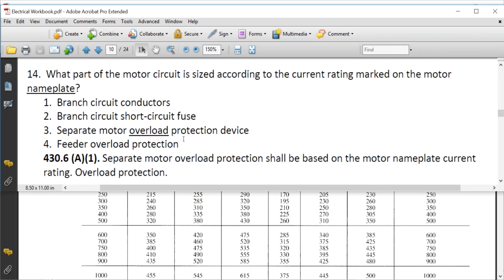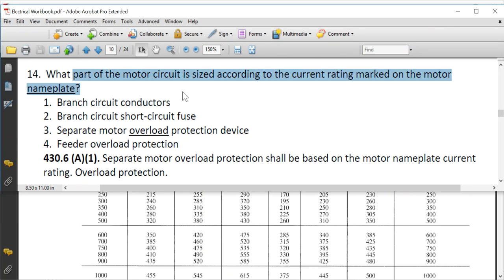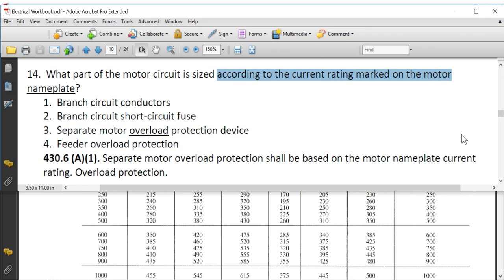What part of the motor circuit is sized according to the current rating marked on the motor nameplate? The correct answer is the overload. The overload is sized from the nameplate, not the tables.